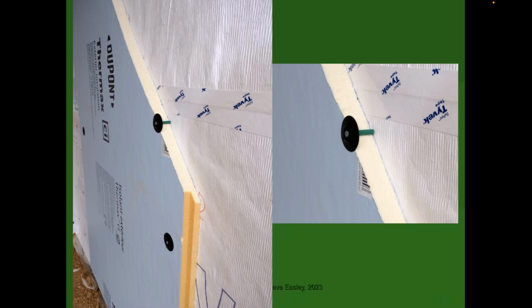So just, here's my wall system. I'm simply doing a stucco wrap material over the top of my OSB, and then I'm going over that with 1.5 inches of polyiso for my exterior insulation. It's tongue and groove, and then I'll go over that with a rain screen lath system, and then stucco is very popular in my area, so I'll go over that. So I'll essentially have R12 on my interior wall system, and then this is another R10. I'll have a little bit higher than that because I'll probably backfill with some blown fiberglass because my walls are 2x6, and then go over that with stucco.